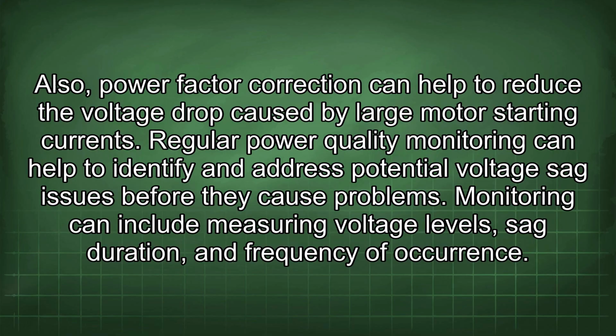Regular power quality monitoring can help to identify and address potential voltage sag issues before they cause problems. Monitoring can include measuring voltage levels, sag duration, and frequency of occurrence.